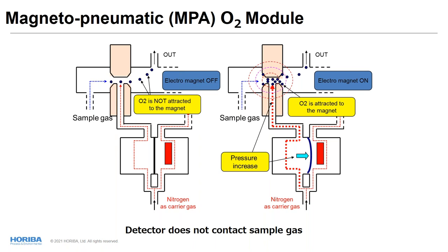The beauty of this method is that the detector does not touch the sample, right? Your detector doesn't touch the sample at all, because the sample flows through this line, which means you don't have to worry about corrosive gases or moisture that may be in the sample. Your detector is not touching that at all. That prevents damage and keeps the MPA detector lifetime longer.